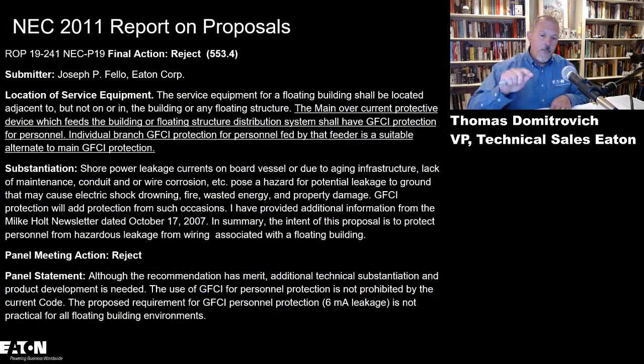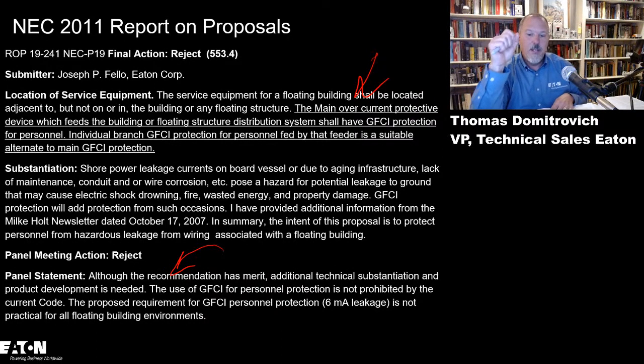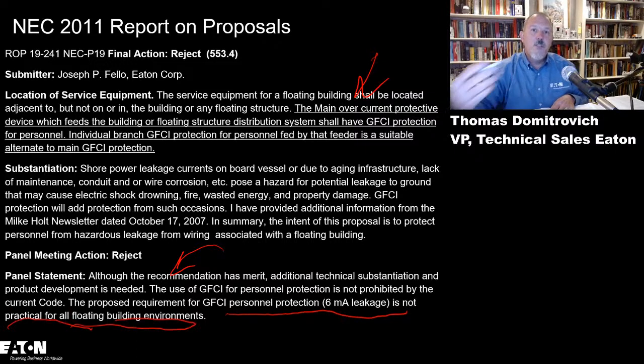Now, it was in the 11 public inputs where Joe Fello, it was probably 2010, or maybe 2011, put that on my desk, and we came up with the language that the main overcurrent protective device, which feeds the building or floating structure distribution system, shall have GFCI protection. So we went straight to GFCI. I knew it didn't have a snowball's chance, but I was interested to see what the panel would say, and what they said was really interesting. They said, although the recommendation has merit, and I'm like, that is a good sign because they recognize there is a hazard, but they also recognized that the proposed requirement for personnel protection is not practical for all floating building environments because of the leakage currents involved.